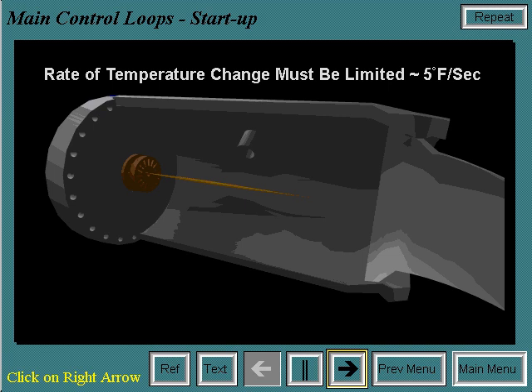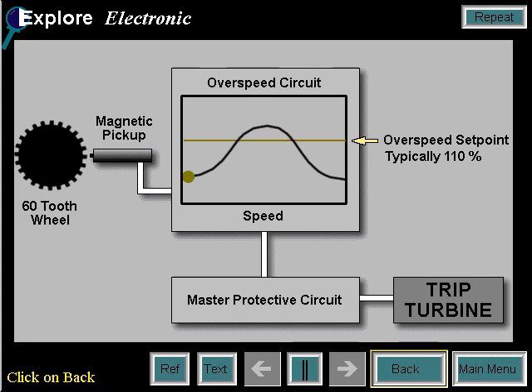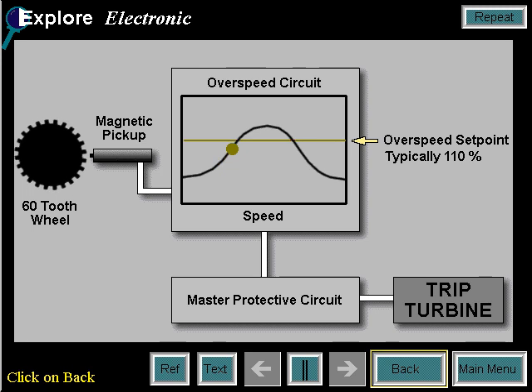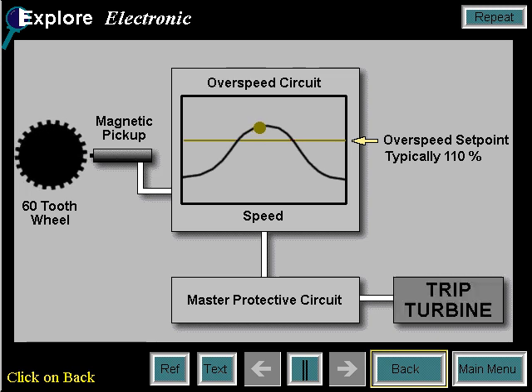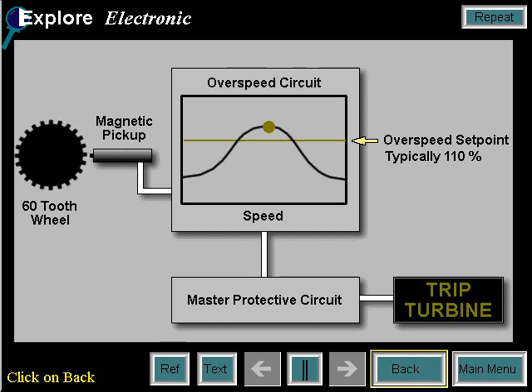The electronic overspeed protection function is performed as shown here. The turbine speed signal derived from the magnetic pickup sensors is compared to an overspeed setpoint. When the turbine speed signal exceeds the setpoint, the overspeed trip signal is transmitted to the master protective circuit to shut down the turbine. An electrical overspeed trip message will be displayed.